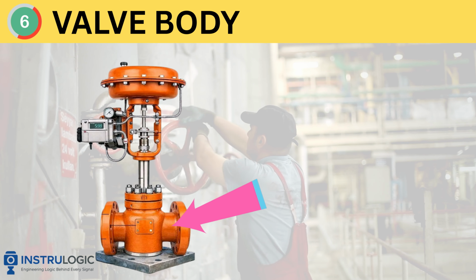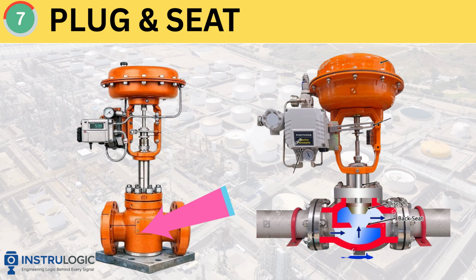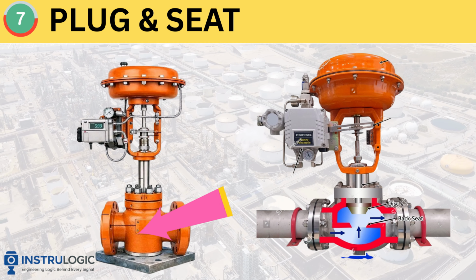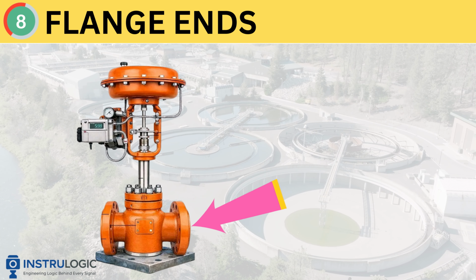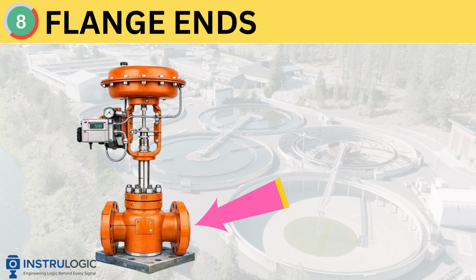The valve body is the main pressure-containing part. This is where the fluid flows through. The plug moves up or down to regulate the flow rate. When the plug moves down, it restricts flow. When it moves up, it allows more flow. The seat provides a tight shutoff when the plug closes. This prevents leakage. These flanged ends connect the valve to the pipeline. They ensure a secure and leak-proof connection.